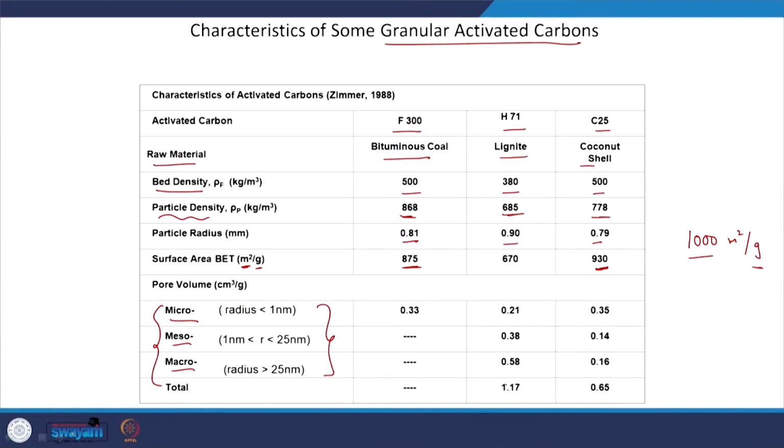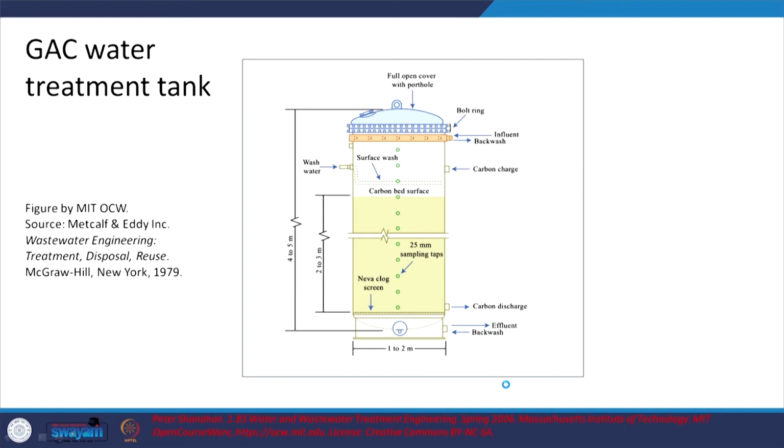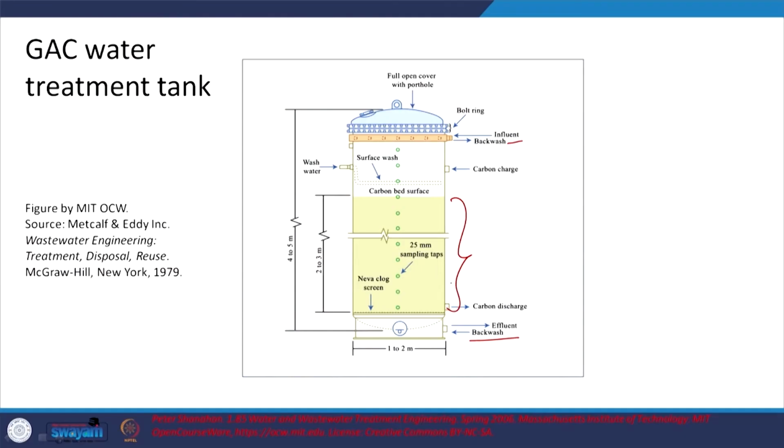So, that is what you have out here, and this is a typical activated carbon tank. There are different ways, bottom up or top to bottom. Here you have the influent from top to bottom and then some head and it comes out here, or sometimes it is going to be pressured and pumped up. There are different ways to understand when this activated carbon has been exhausted, as in this is my media here. As the water passes through, the compounds or the adsorbate in the solution are adsorbed onto the adsorbent, which is the granular activated carbon. So, after time this will be exhausted.